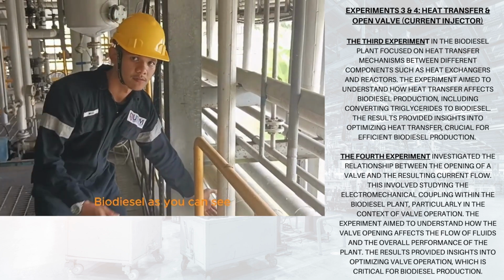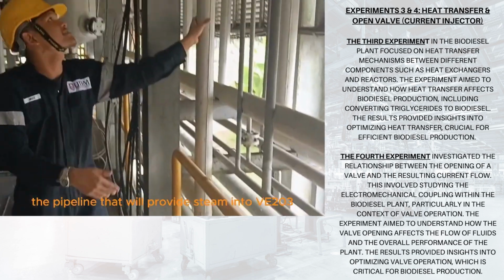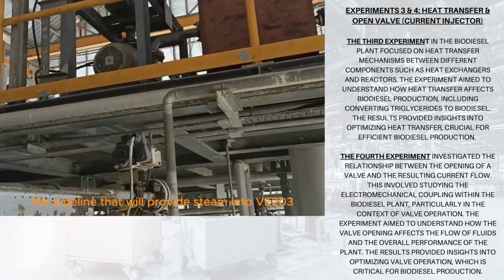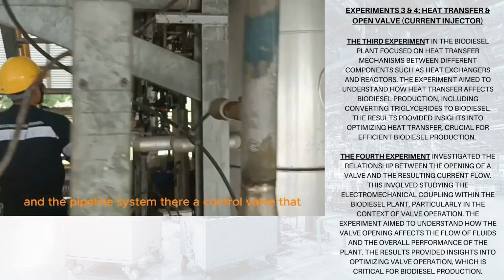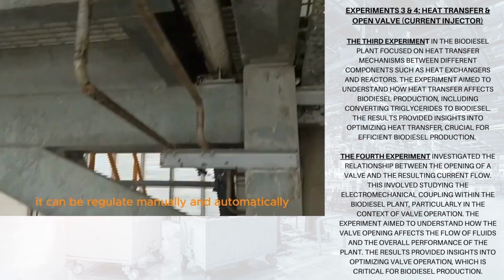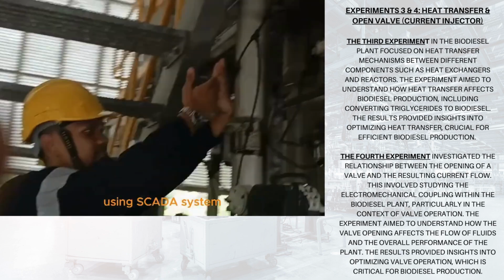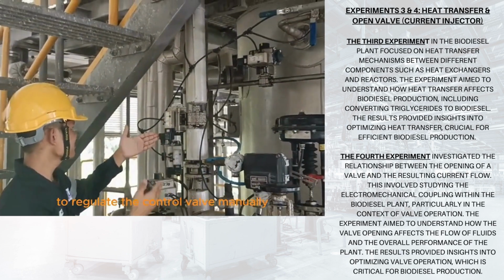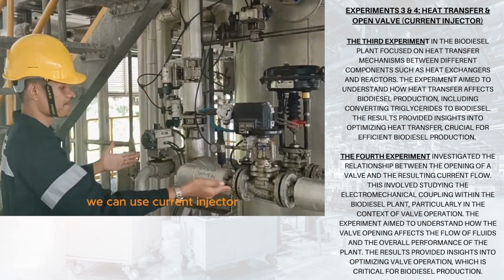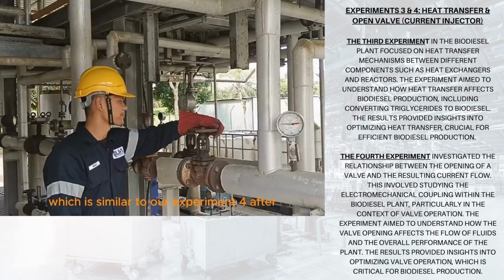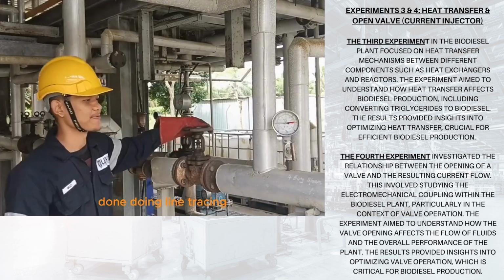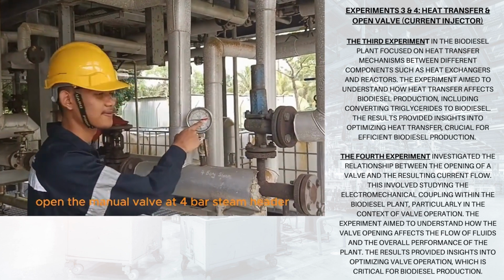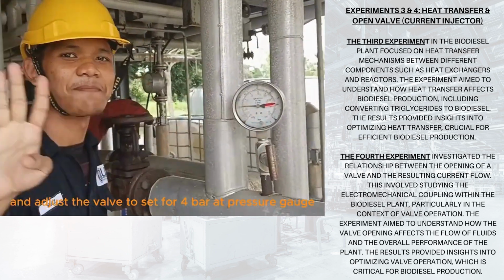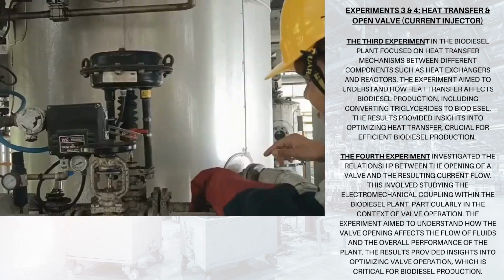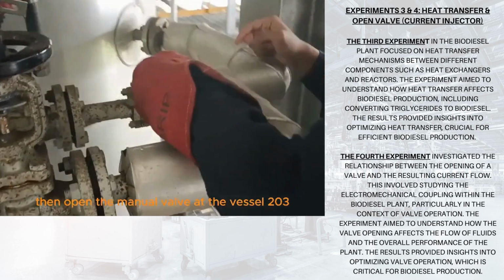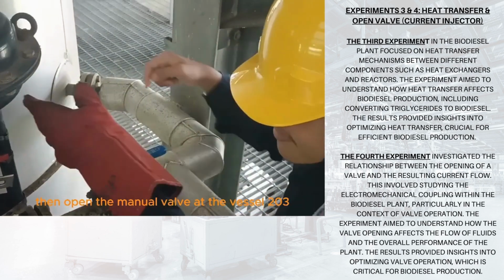As you can see, this is the pipeline that will provide steam into VE203. In the pipeline system, there is a control valve that will control the steam. It can be regulated manually and automatically using the SCADA system. To regulate the control valve manually, we can use a current injector, which is similar to our experiment 4. After line tracing is done, open the manual valve at the 4-bar steam header and adjust the valve to set 4 bar at the pressure gauge. Then open the manual valve at vessel 203.